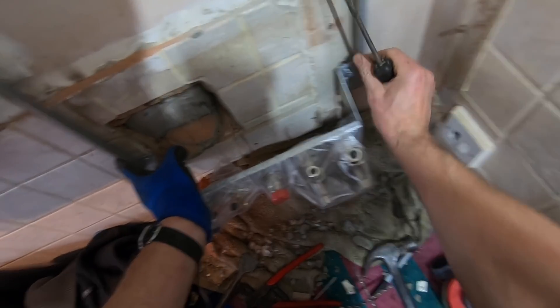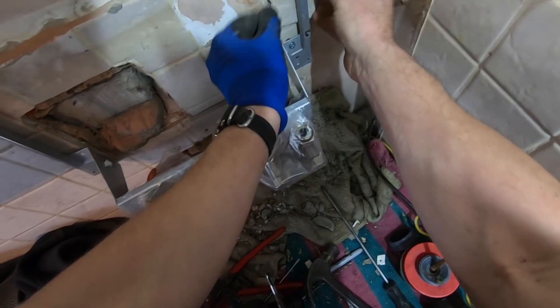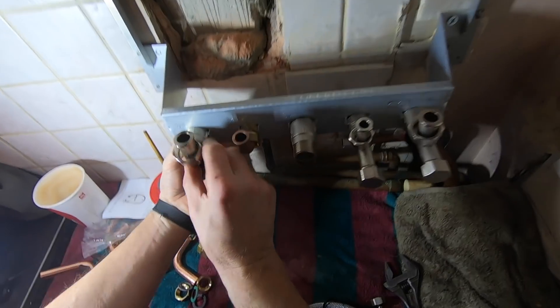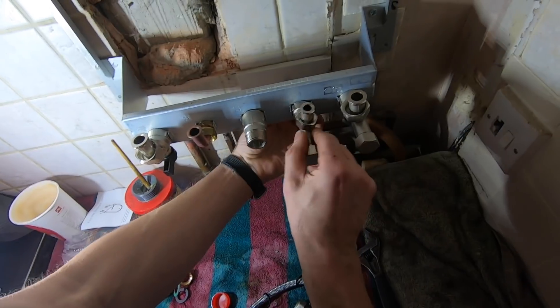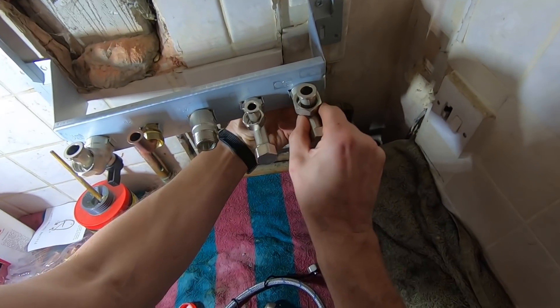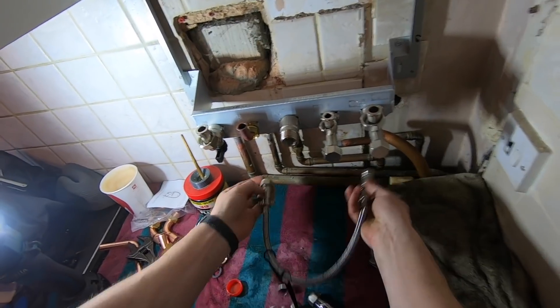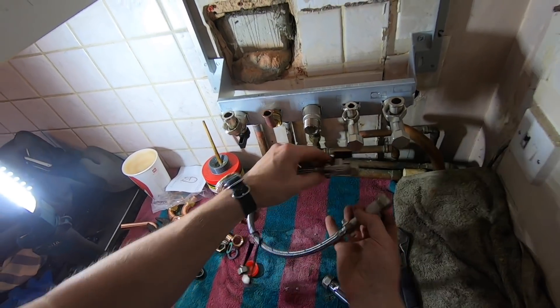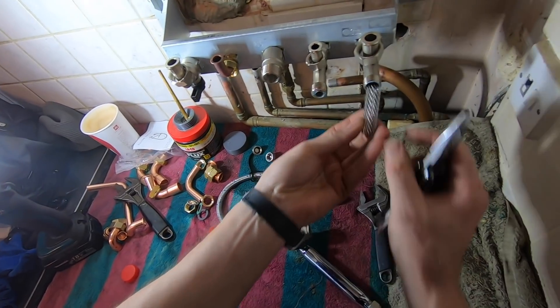This one wants to be packed off the wall because of these tunnels. I loosen off the back nuts around the back, and these can jiggle a little bit because when you come to fit them to the boiler you tend to find that they want a bit of backwards and forwards movement and left and right. So loosen the back nuts on the filling loop, and normally when you're doing this you can actually fit it underneath here — and that's how it should look. Nice and clean.